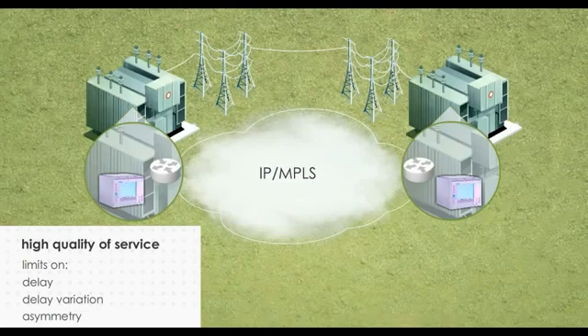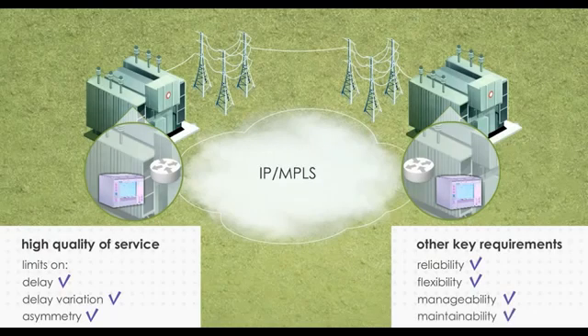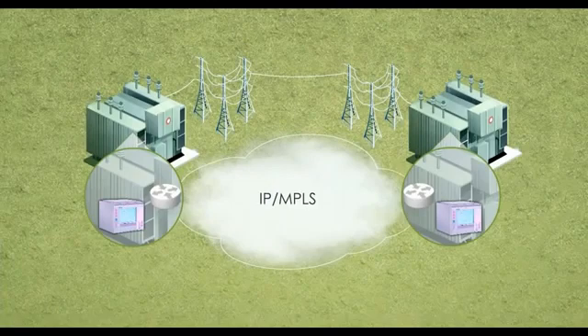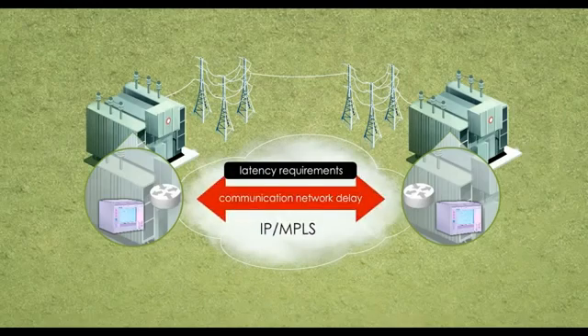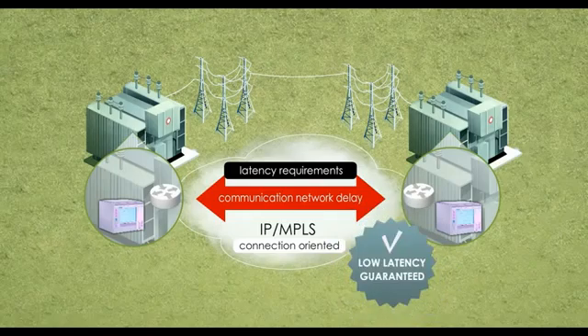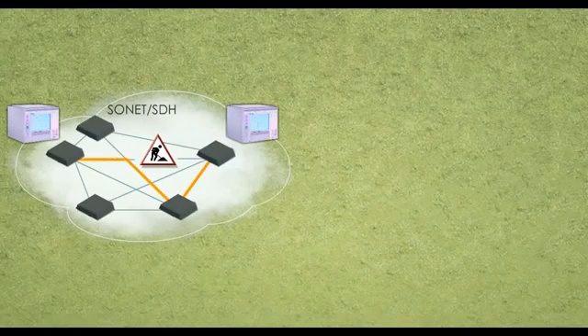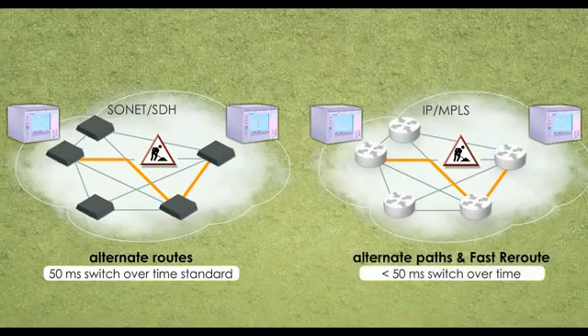An IP MPLS network can meet these as well as other key requirements such as reliability, flexibility, manageability, and maintainability. A major concern for utilities is whether the IP MPLS network can meet the strict latency requirements for protection signals between transmission substations. Unlike traditional best effort connectionless IP technology, IP MPLS is connection oriented and capable of guaranteeing low latency service. Sonet SDH networks can be provisioned to provide alternate routes for mission critical traffic, providing less than 50 milliseconds switchover time when operating correctly. IP MPLS networks support alternate paths and fast reroute with sub-50 milliseconds switchover time.